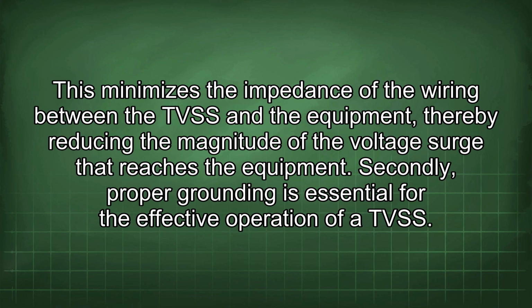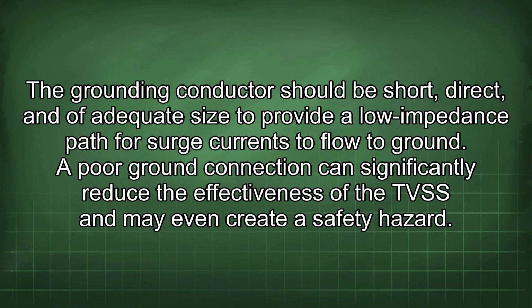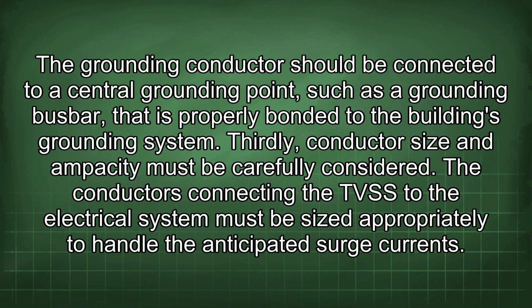Secondly, proper grounding is essential for the effective operation of a TVSS. The grounding conductor should be short, direct, and of adequate size to provide a low impedance path for surge currents to flow to ground. A poor ground connection can significantly reduce the effectiveness of the TVSS and may even create a safety hazard. The grounding conductor should be connected to a central grounding point, such as a grounding bus bar, that is properly bonded to the building's grounding system.